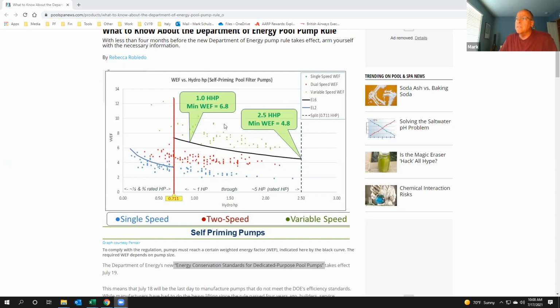So basically these are all the self-priming pumps in the US market, plotted by hydraulic horsepower versus weighted energy factor. Both of these terms are what the government's using now to determine whether a pump is compliant with the new regulations. You can see the single speeds are way down here because they have low weighted energy factors, the dual speeds are a little bit higher, and the variable speeds are much higher.